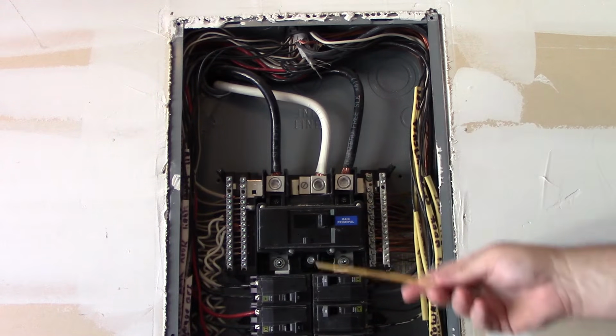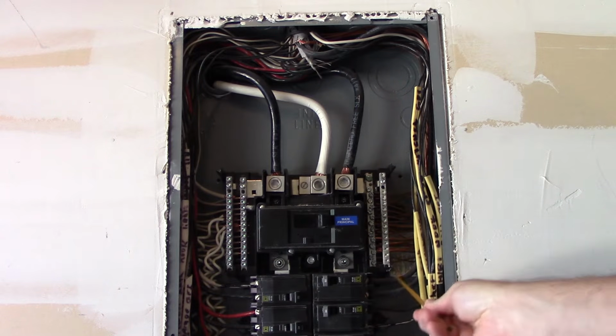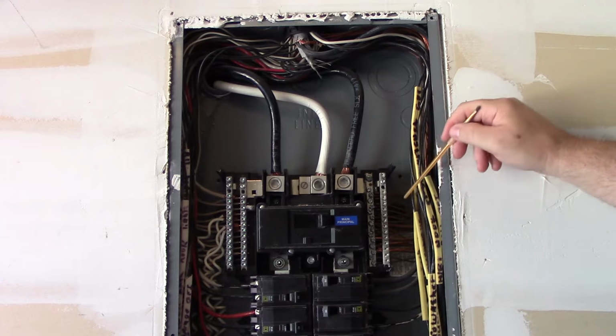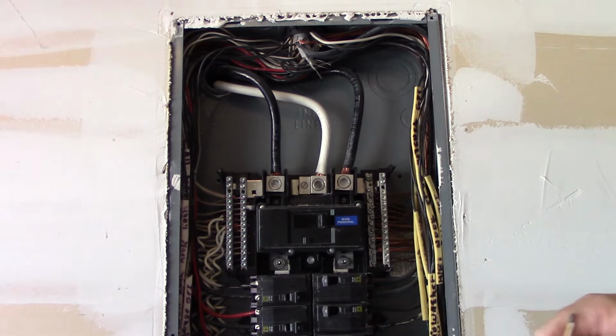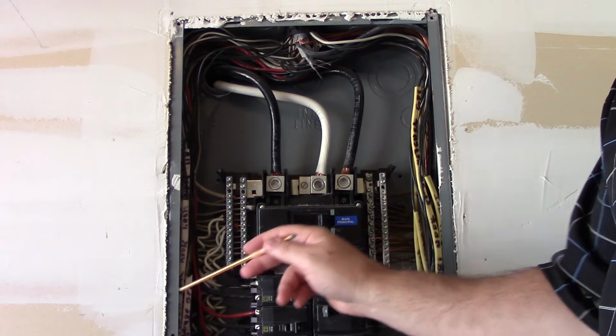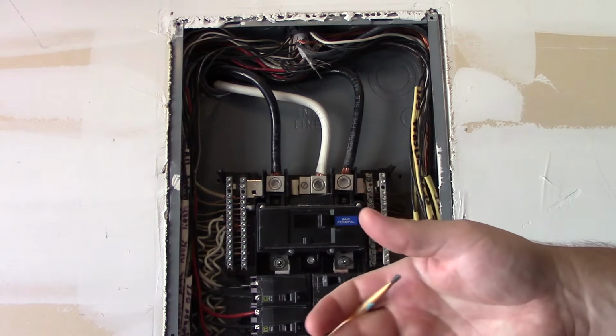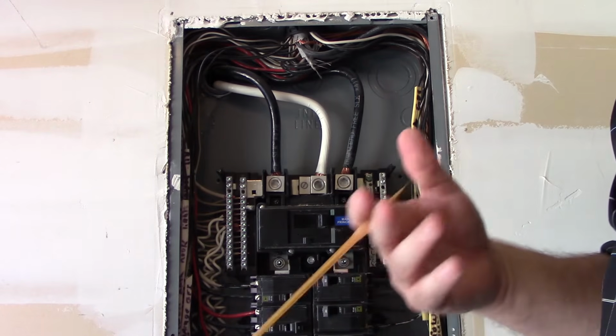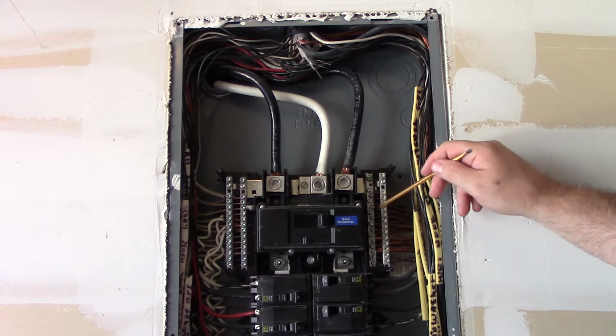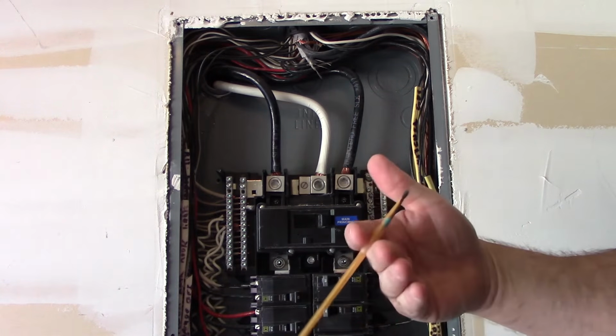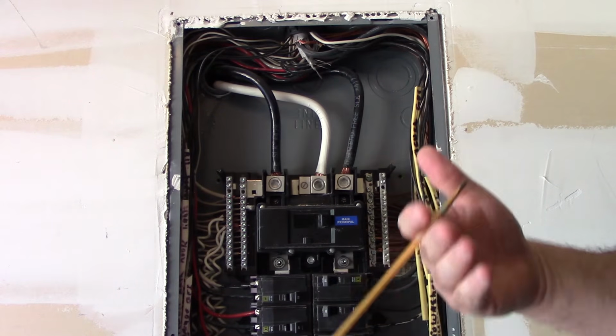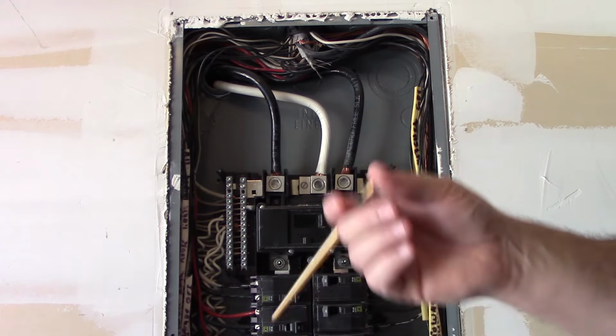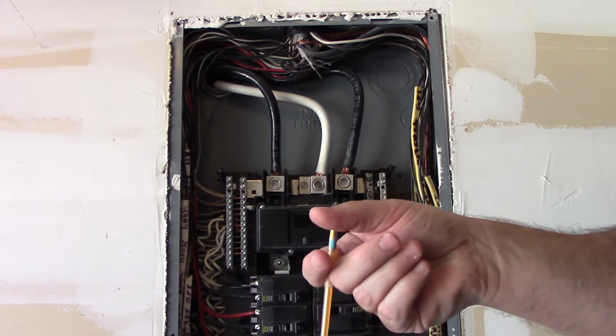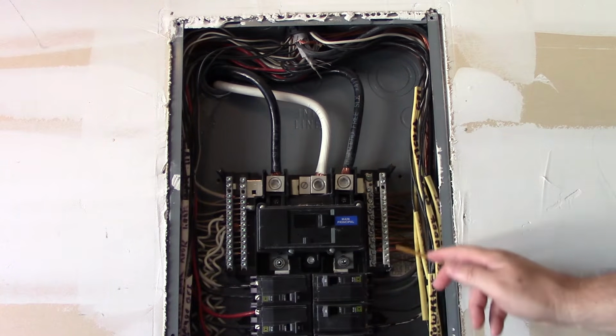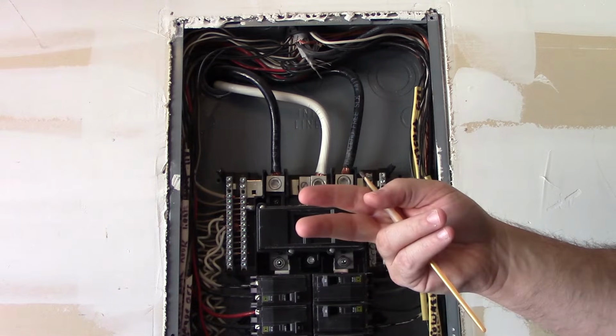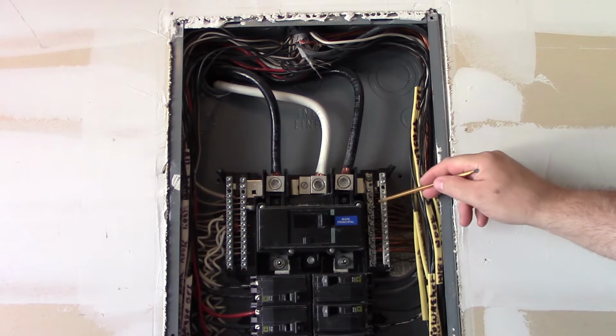So if I'm a municipal guy, I'm going to come in here and make sure that all of these are terminated and nothing's loose in here. Now, how many of these equipment grounded conductors can I have per terminal? This panel has a directory on the inside of the cabinet that tells me I can have up to two 14s or two 12s under the same terminal lug, or up to two 12 aluminums if I had aluminum branch circuits in here. It doesn't tell me that I can terminate a 14 and a 12 under the same lug, and there is no way it can torque properly on the 14 gauge if it's also terminating onto a 12 gauge. It's just different sizes, so the torque cannot happen. So that's an issue, and we want to make sure they're the same size. Two 14s under this screw are okay, or two 12s are okay, but I can't have a 14 and a 12 sharing it.